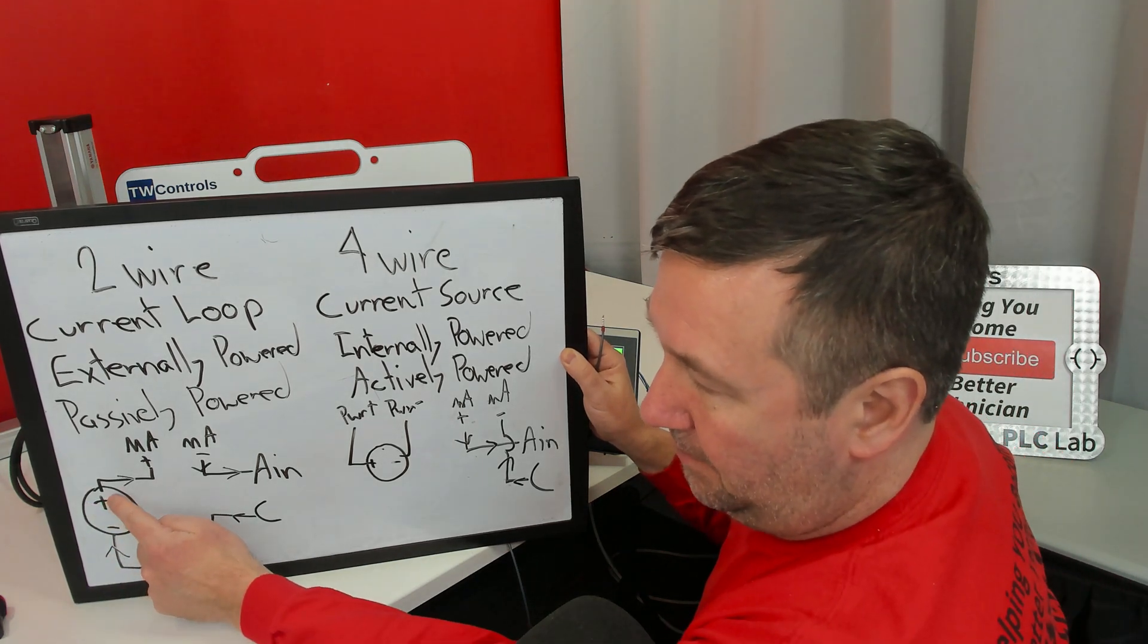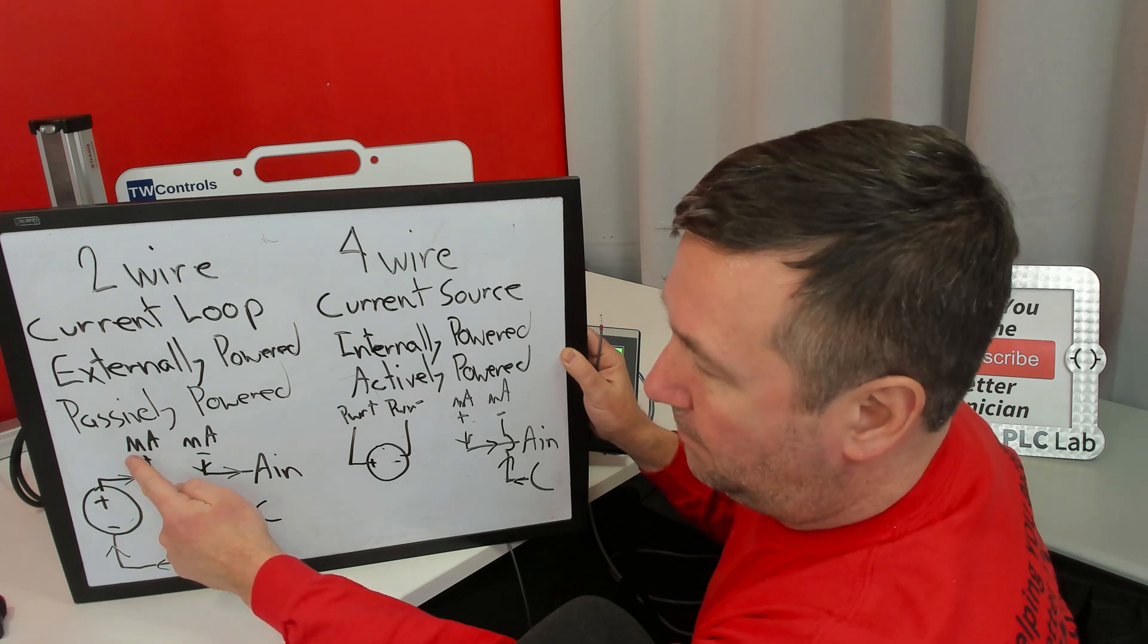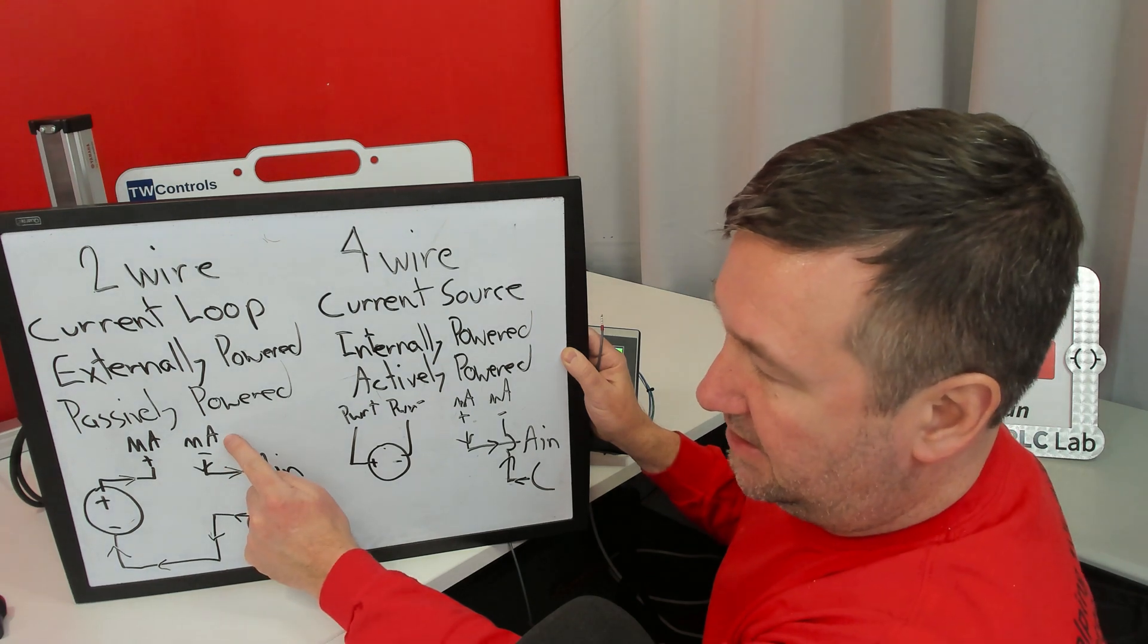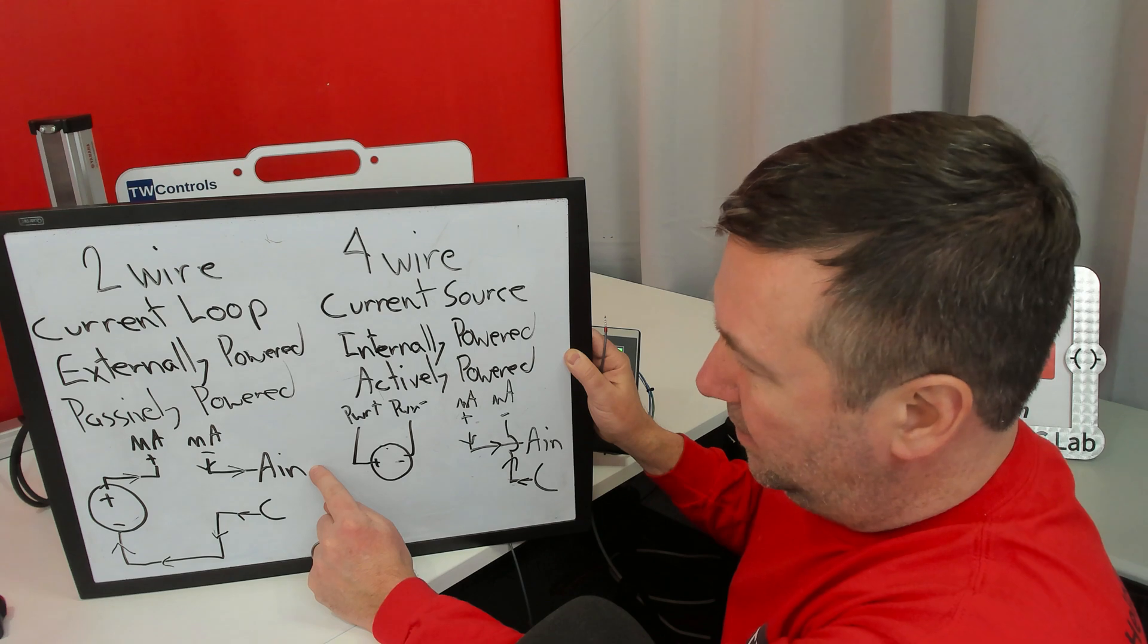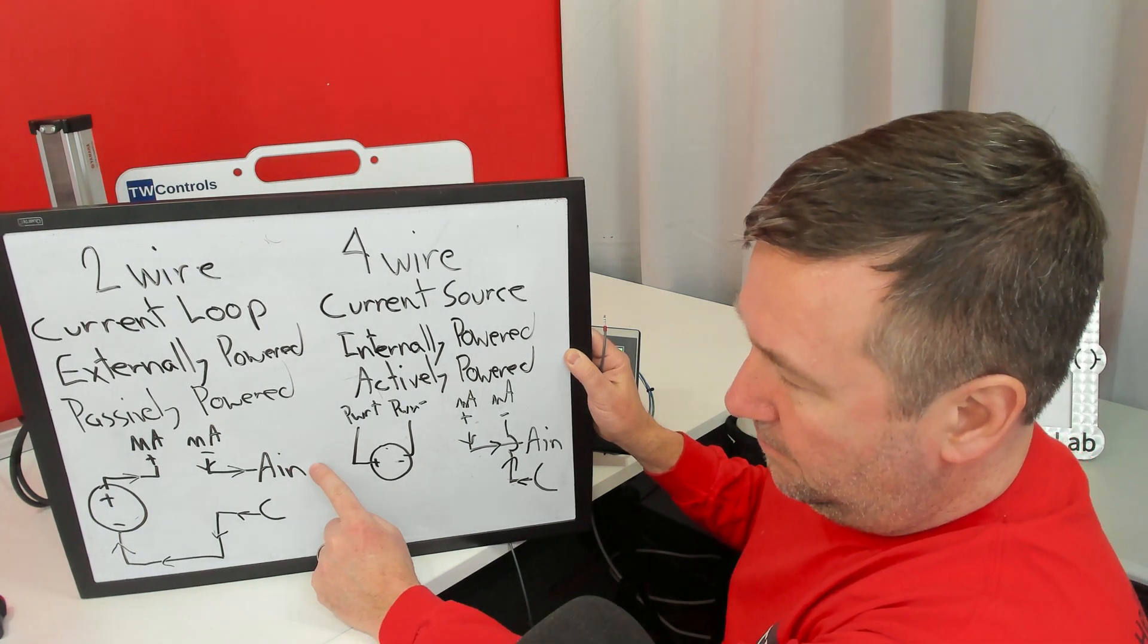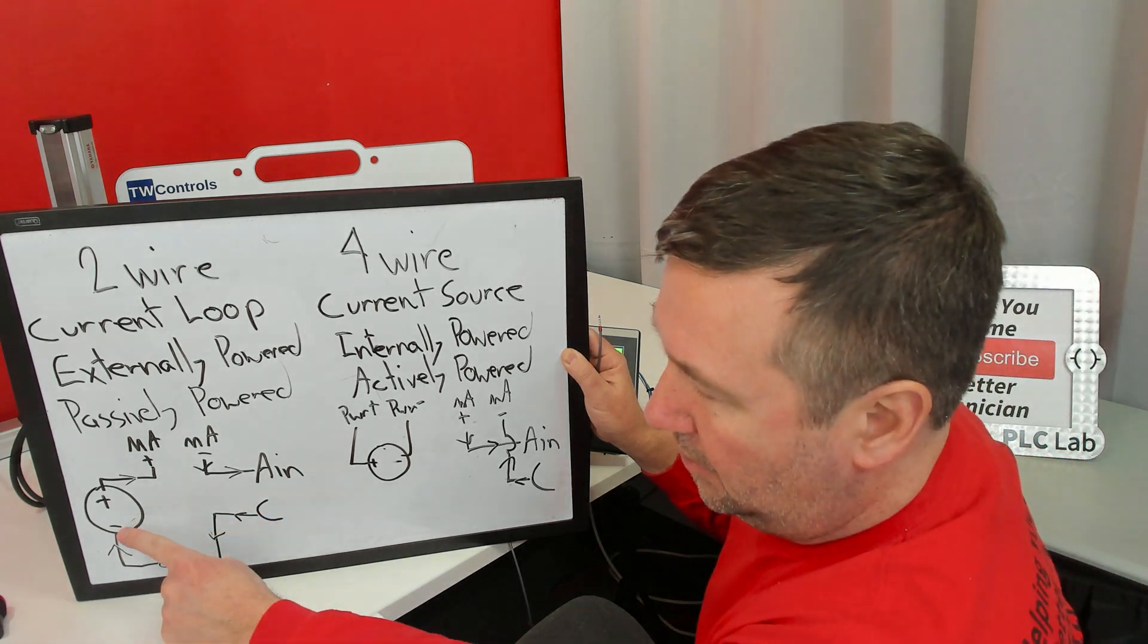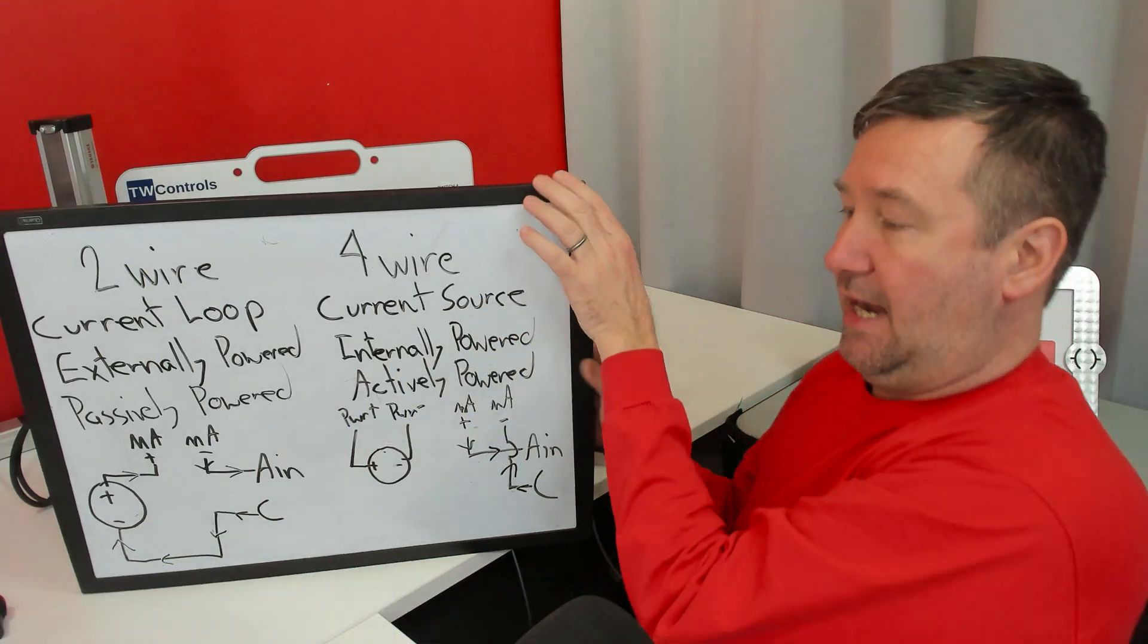So this will be my PLC trainer's power supply. This is going to go to the black post on our PLC trainer. Then we're going to take the red post and keep it on the analog input. And analog input, which is pin one, and we'll take pin two back to the minus of our PLC trainer's power supply.